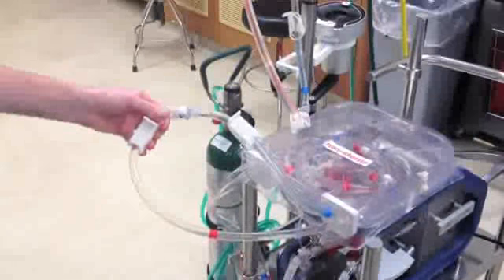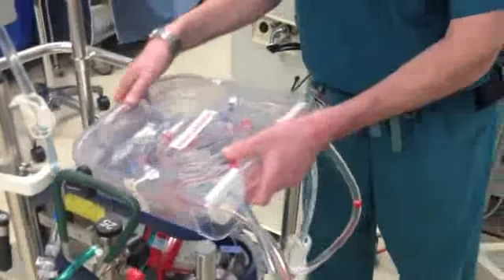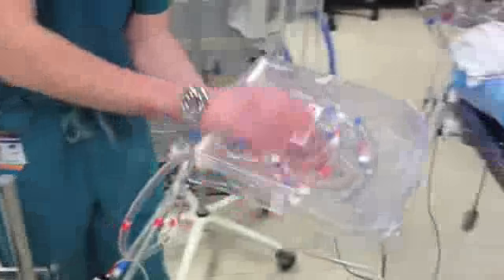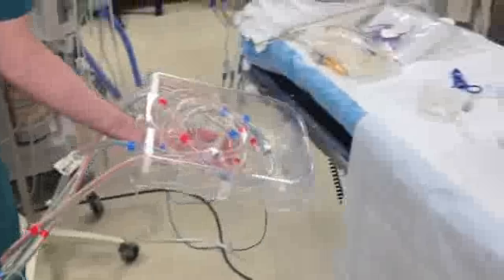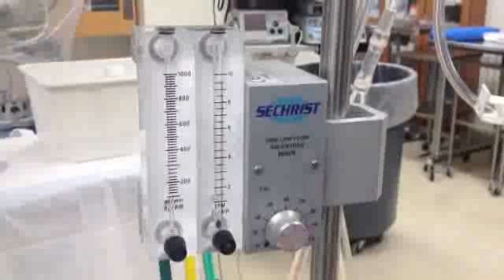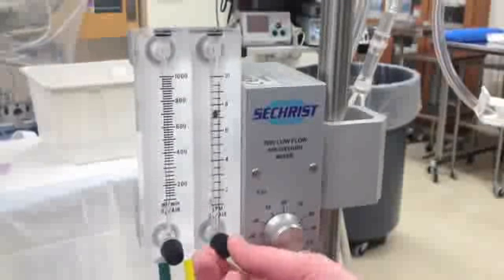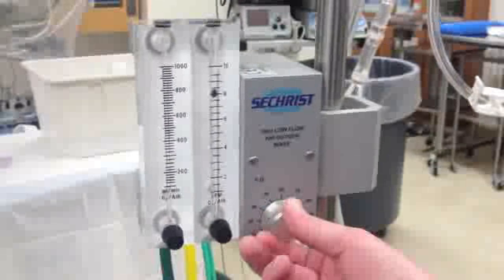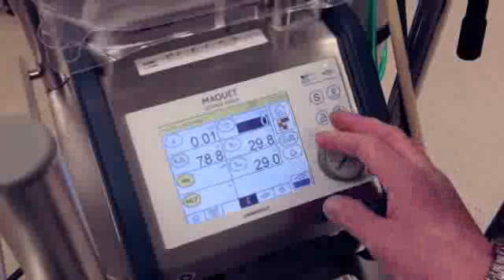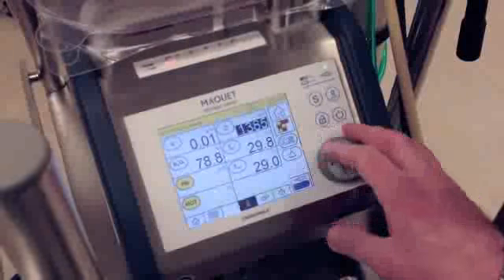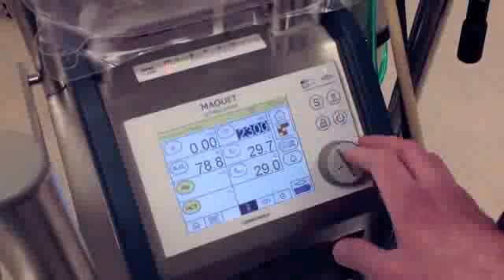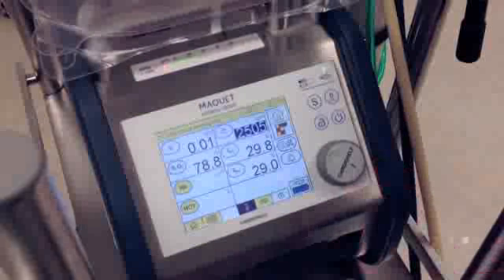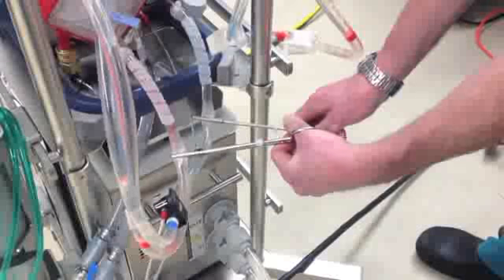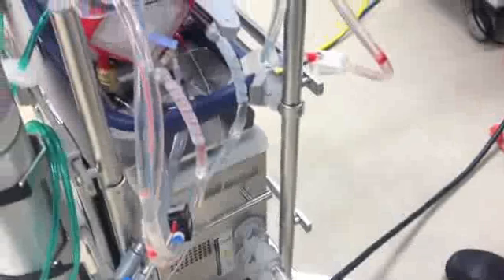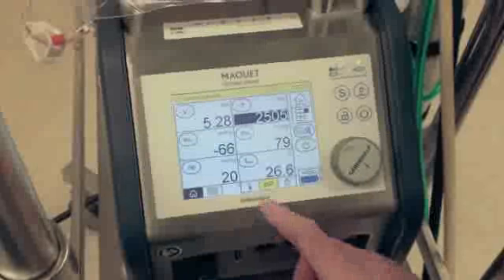There you go. There's your circuit. And that's ready to be passed to the sterile field. Just take the tray off, remove the lid, and the folks at the sterile field will know what to do from there. Your next step will be to turn up your sweep. This is sweep here. You want it anywhere from 8 to 10, and you'll turn your FiO2 up, which was the knob to the right, to 100%. Then you'll increase your flow, your RPMs, to about 2,500. And that's to prevent any kind of backflow. And then you unclamp once the folks at the sterile field are connected and they say go ahead and start flowing.